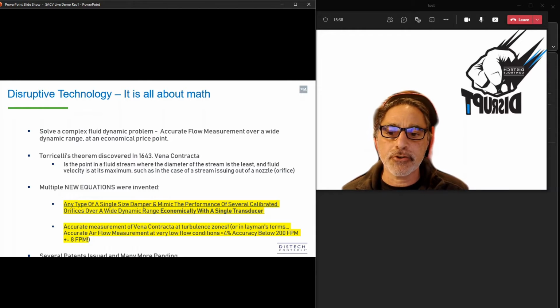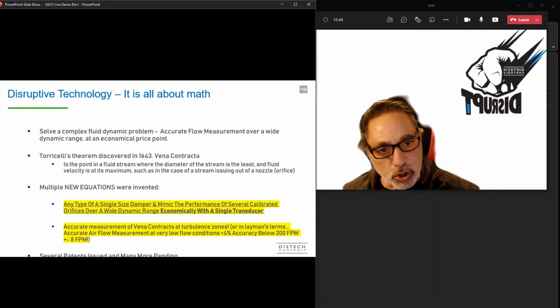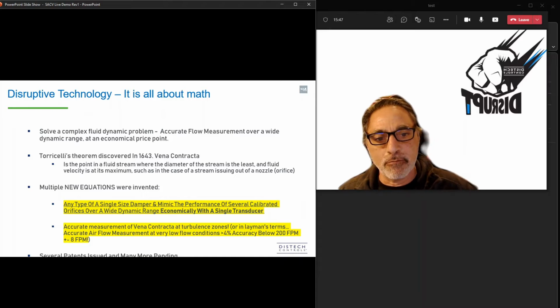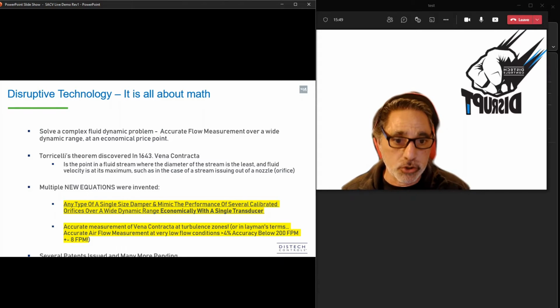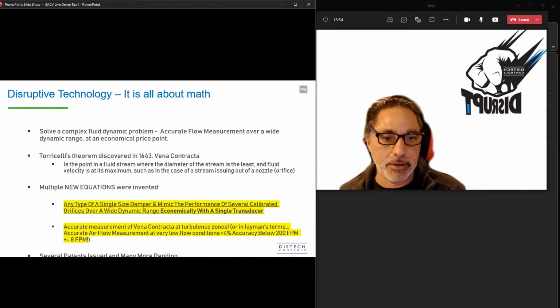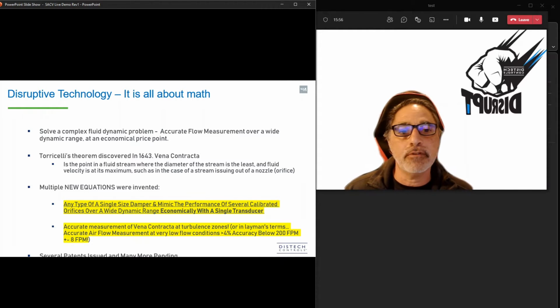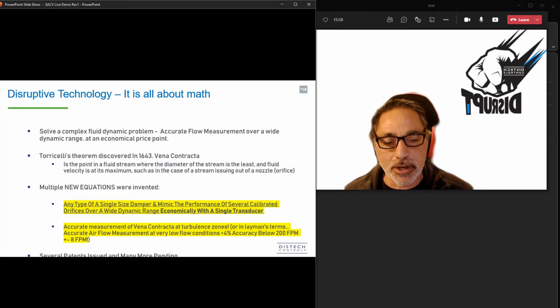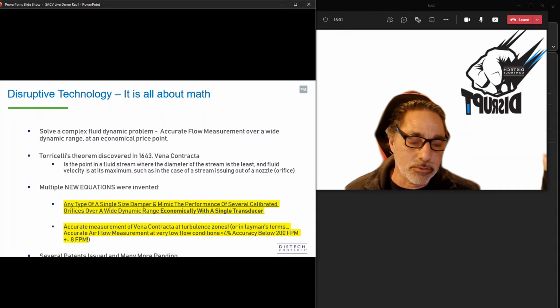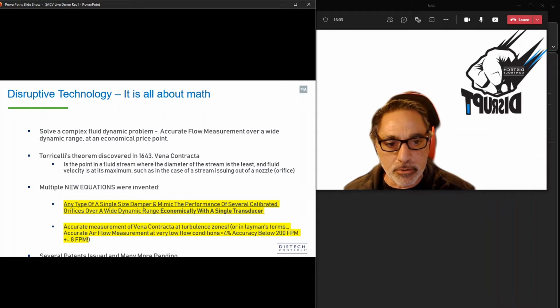And then having that accurate measurement around the vena contracta, which is basically in the turbulence zone. That turbulence zone is when you close a damper and now you have more turbulence happening, and that's what you're trying to drive to at the lower CFM. And that's where the accuracy becomes very important. With traditional VAV boxes, the reason you have so many different sizes, from 4-inch all the way up to 26, 28 inches, depending on round or whatever rectangular size you may have, is driving to that lower CFM with an accurate reading.